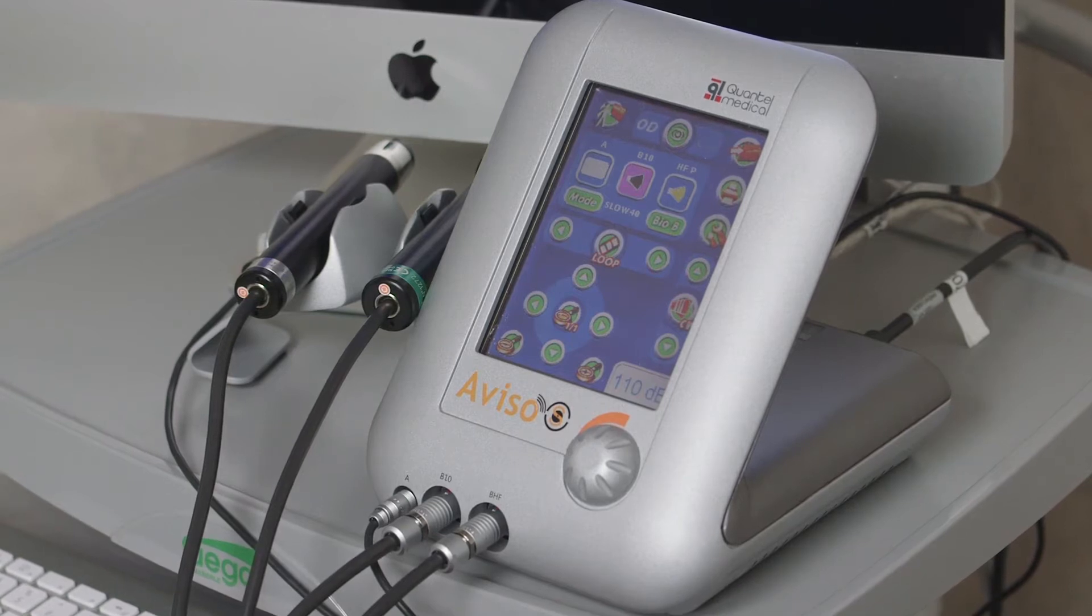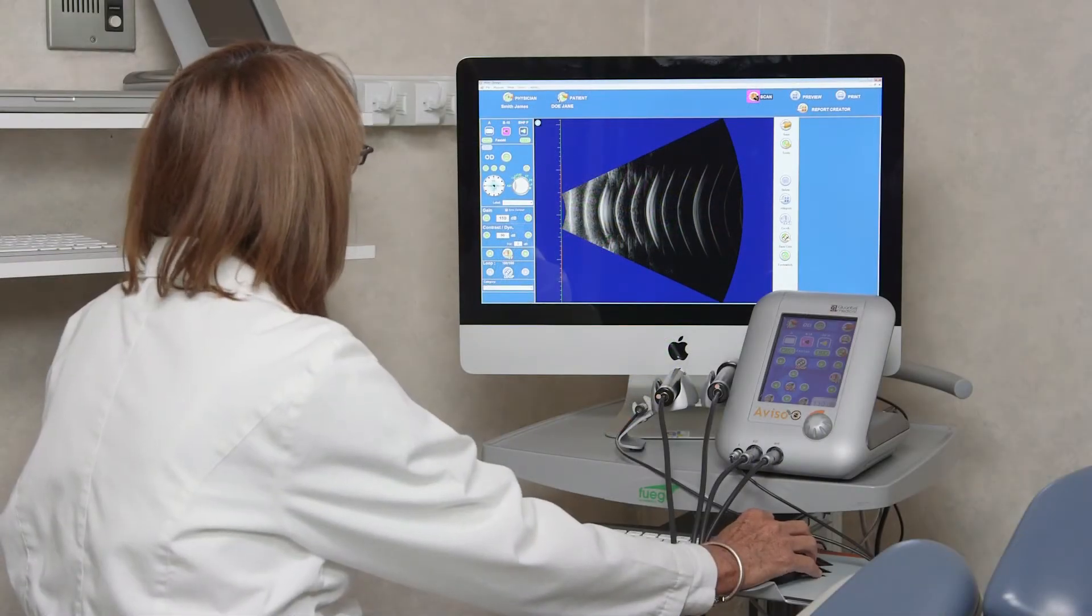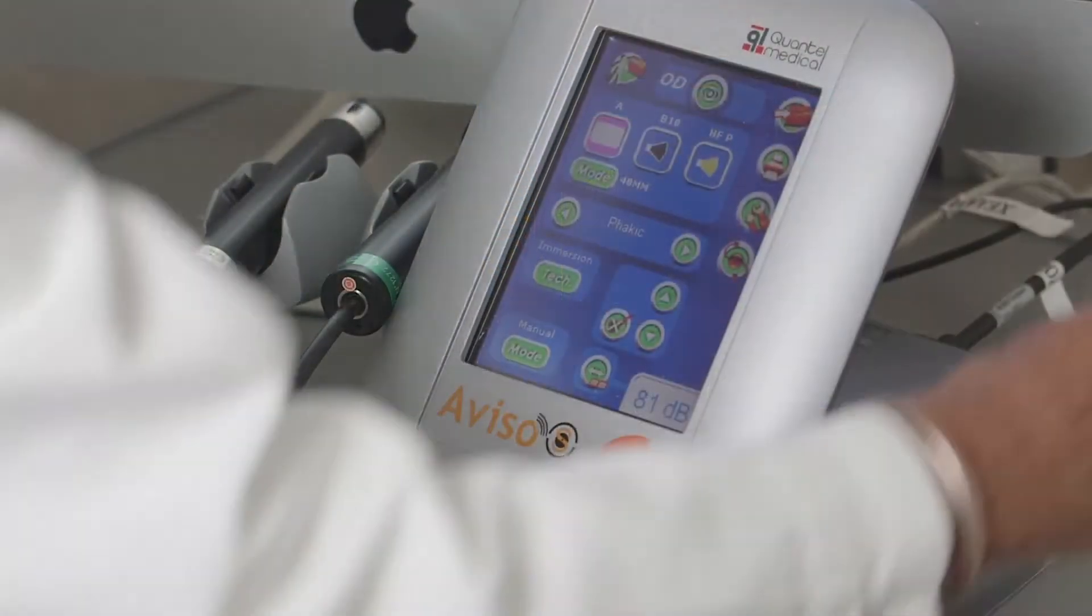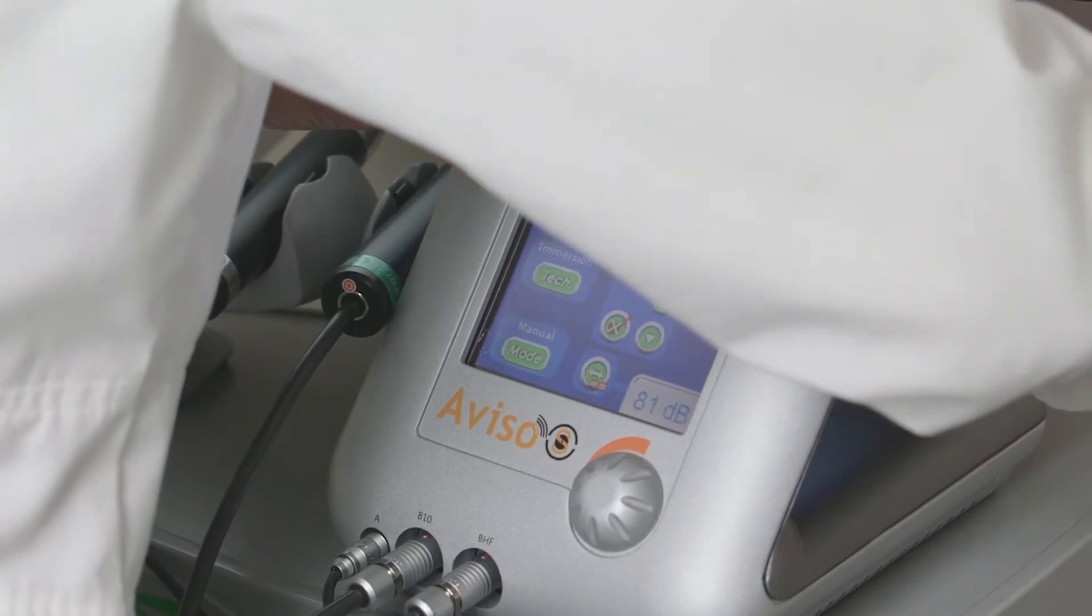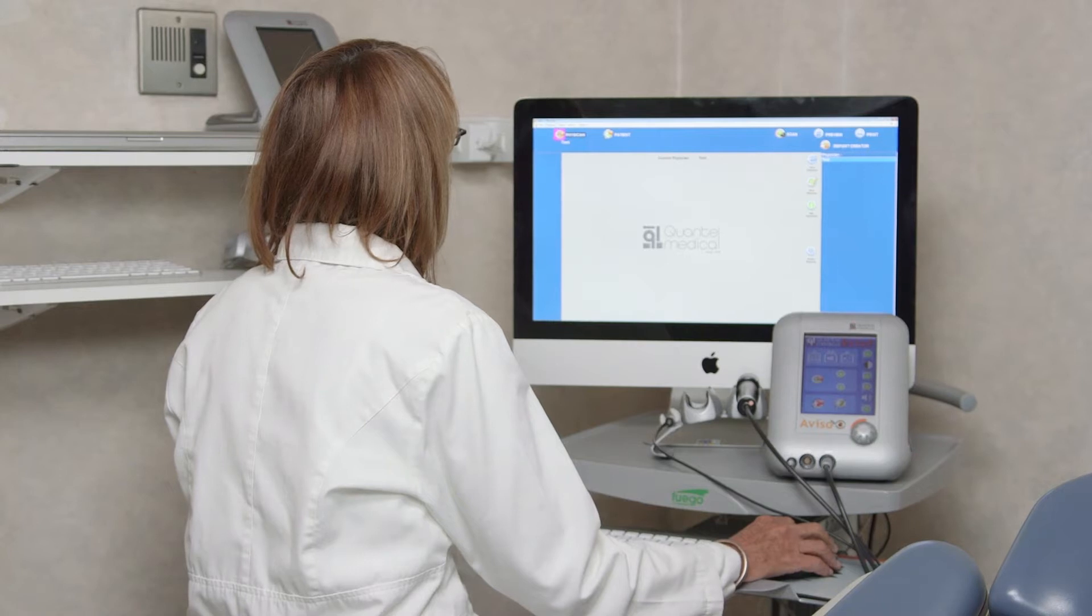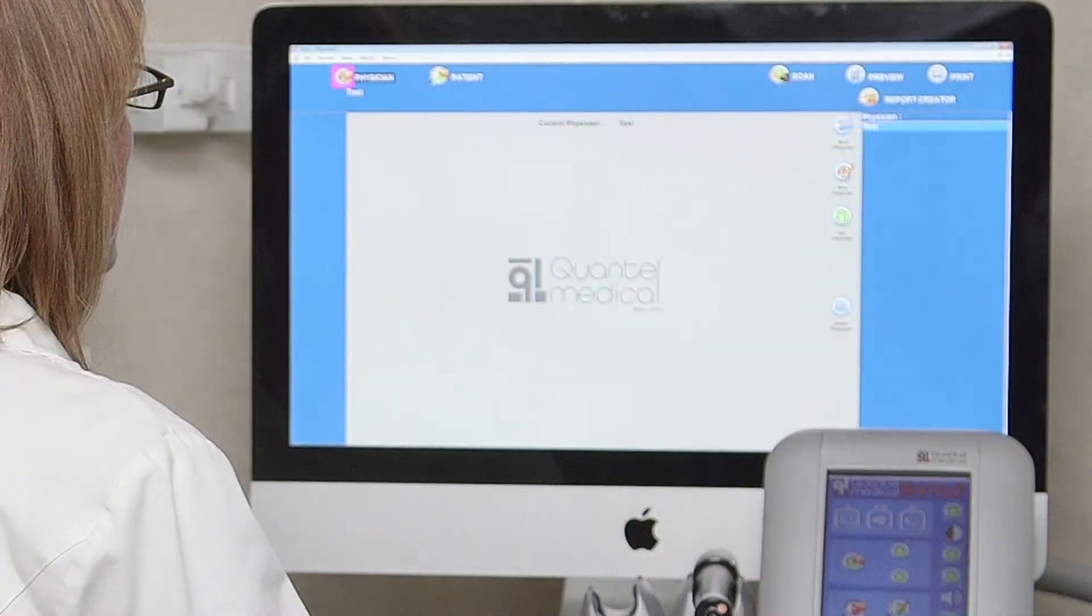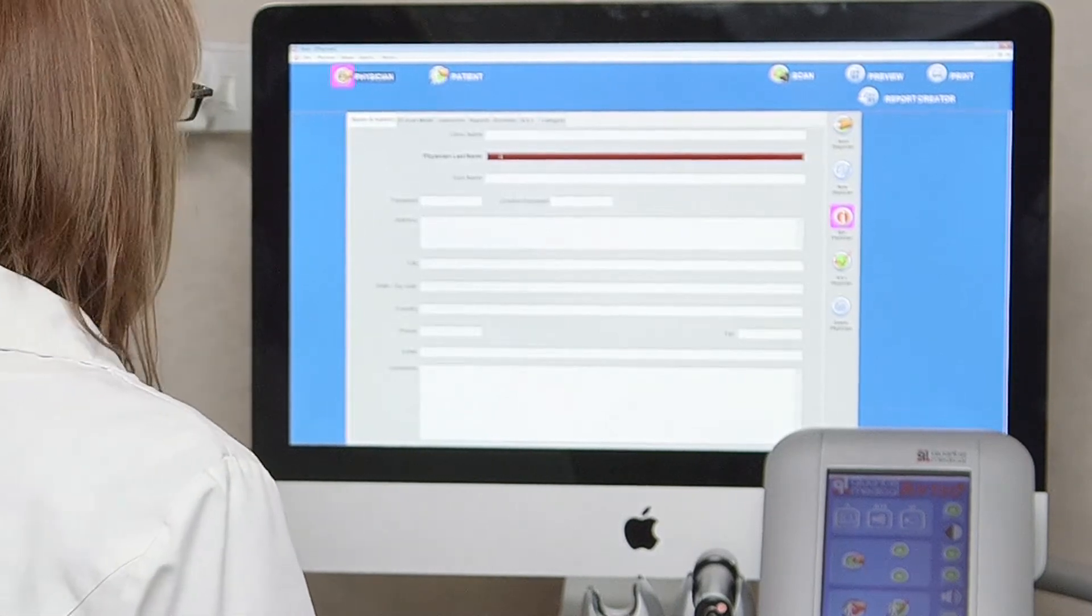The Aviso-S is designed to be connected to a laptop or desktop computer where exams, images, and reports are displayed. Image acquisition can be controlled via the computer or touchscreen. We start by turning on the main unit via the power switch on the back. Once the unit is switched on, the connected computer should automatically open the Aviso-S software application. The software can also be accessed via the Aviso-S shortcut icon on the computer's desktop.